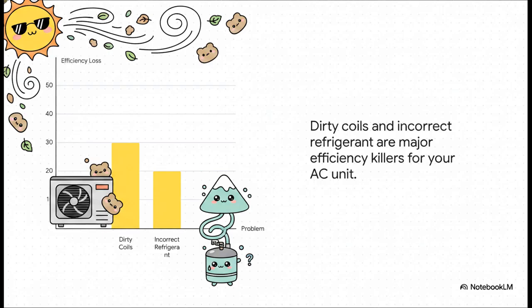Then summer rolls around and the problems just change shape, but they're every bit as serious. Remember those high winds we talked about? Well, they coat your AC's outdoor coils in a layer of dust and gunk. That alone can slash its cooling power by a whopping 30%. And then, because of the altitude, if the refrigerant level isn't set perfectly for that thinner air, you can lose another 20% of your cooling efficiency right there.